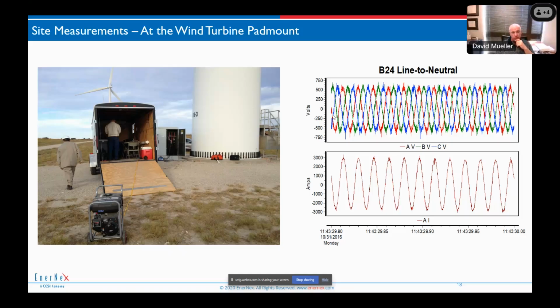Was the transformer manufacturer told that there were going to be harmonics, switching harmonics at 3, maybe as high as 6 kilohertz, that it's going to be exposed to? Are they able to? Clearly, many facilities are able to design transformers that meet these criteria, but some are not. The problems typically start as a high dissolved gas reading where there's something going on with the transformer, and a failure occurs sometimes later.